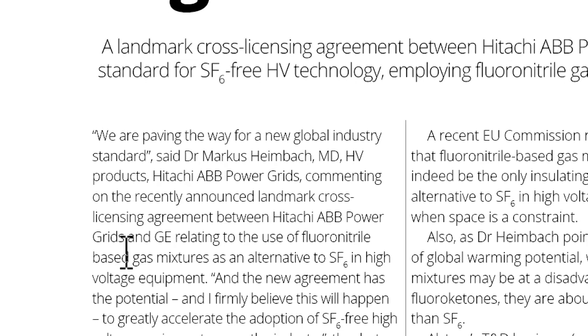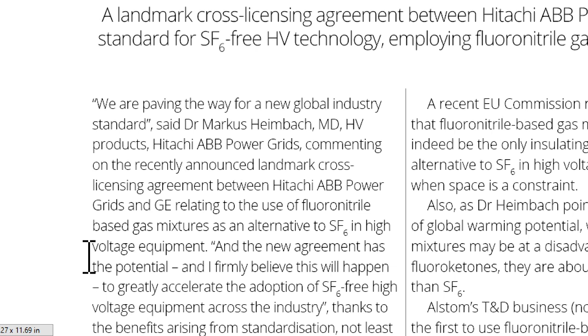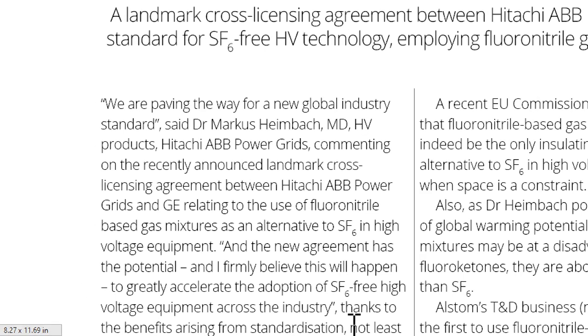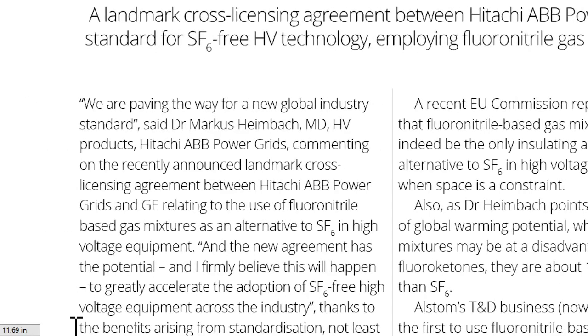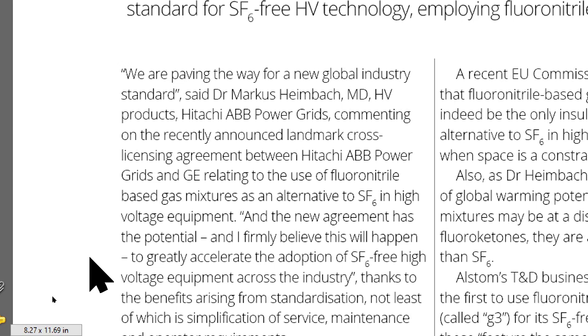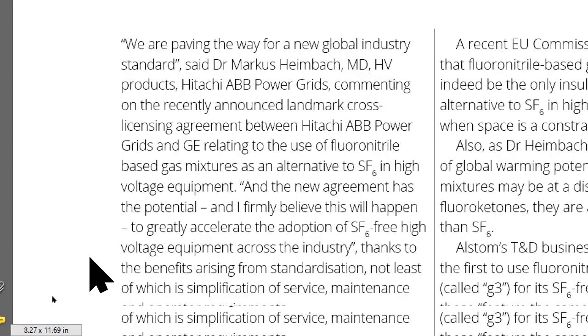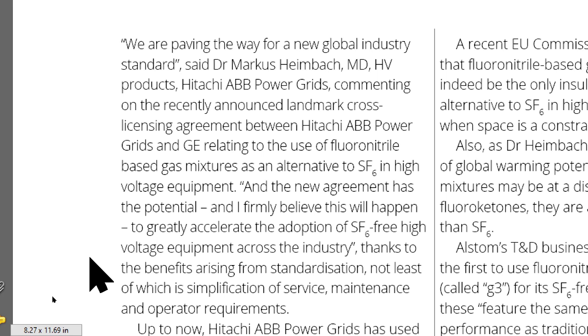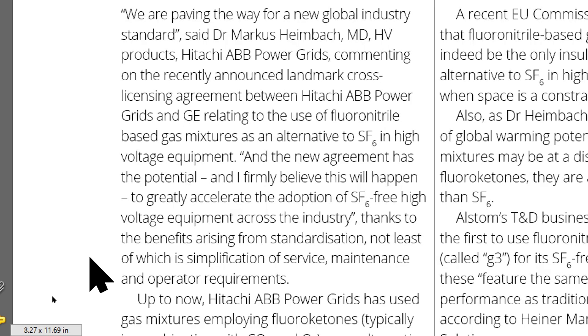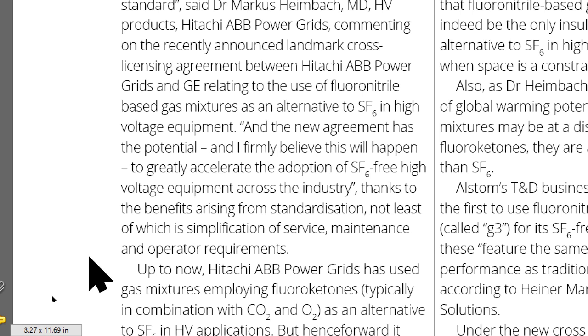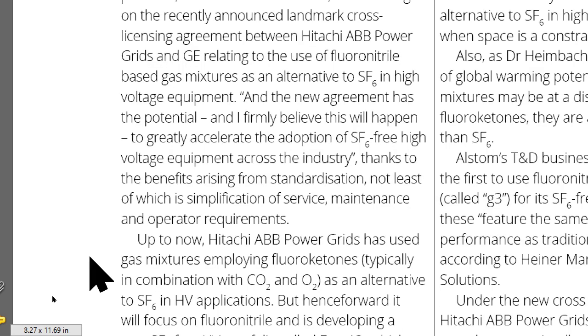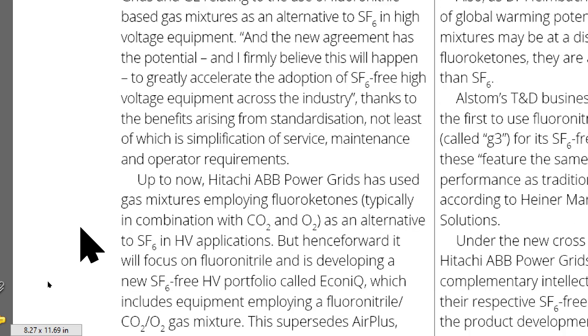We're paving the way for a new global industry standard, said Dr. Marcus Heimbach, MD, HV Products, Hitachi ABB Power Grids, commenting on the recently announced landmark cross-licensing agreement between Hitachi ABB Power Grids and GE relating to the use of fluoronitrile-based gas mixtures as an alternative to SF6 in high voltage equipment. And the new agreement has the potential, and I firmly believe this will happen, to greatly accelerate the adoption of SF6-free high voltage equipment across the industry, thanks to the benefits arising from standardization, not least of which is simplification of service, maintenance, and operator requirements.